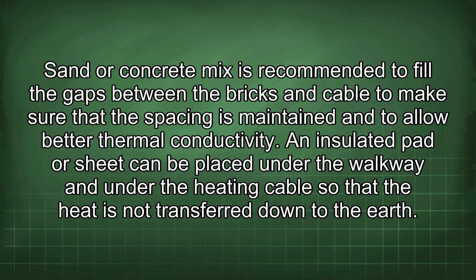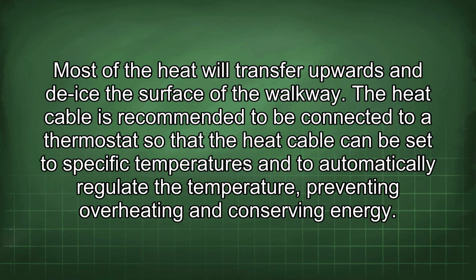An insulated pad or sheet can be placed under the walkway and under the heating cable so that the heat is not transferred down to the earth. Most of the heat will transfer upwards and de-ice the surface of the walkway.